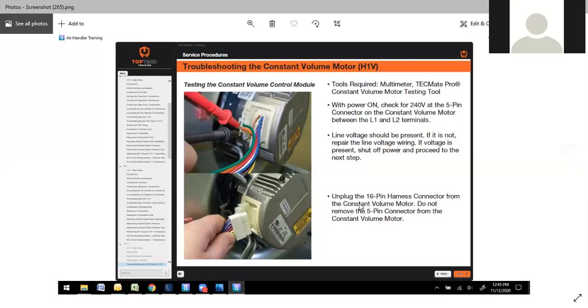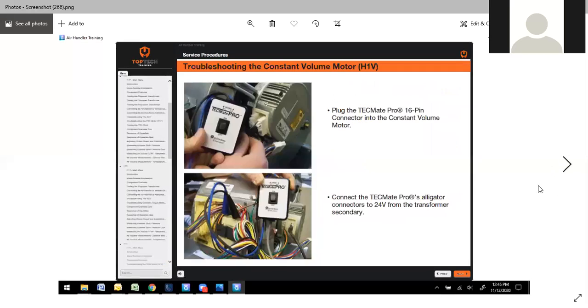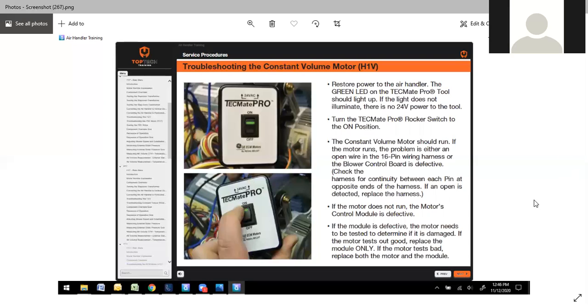Next, you want to do this when the power's off, by the way. Unplug your 16-pin connector. Plug the TECMate into the 16-pin connector. Connect the TECMate's two alligator clips to R and C for 24 volts. At that point, turn the switch on. So at this point, your TECMate is actually powering it up. If you turn the system on, it should run. If the motor runs, the problem is either with the wiring, which is likely doubtful, or you have a bad board that's not sending 24 volts. If the motor does not run, more than likely it's the module that's defective. If the module is defective, if it's under warranty, I think you get the whole motor and the module.